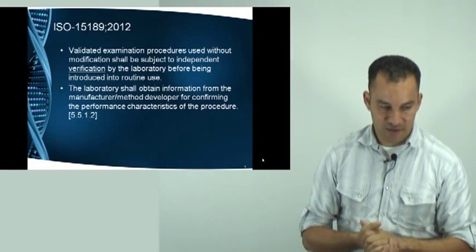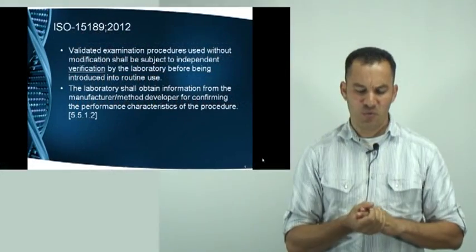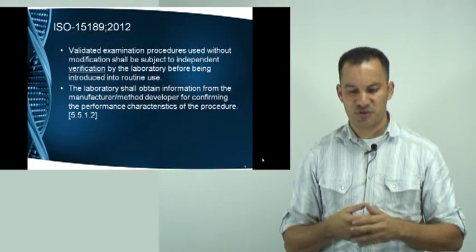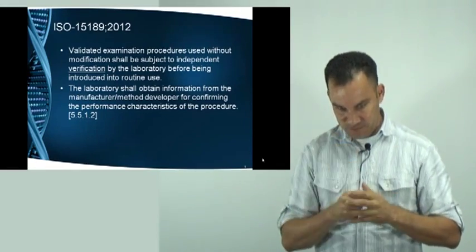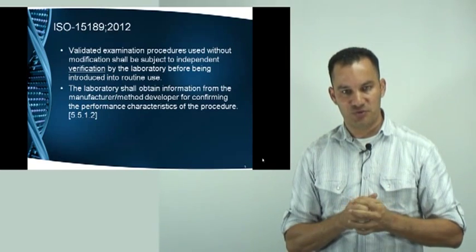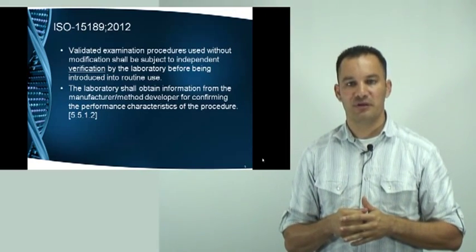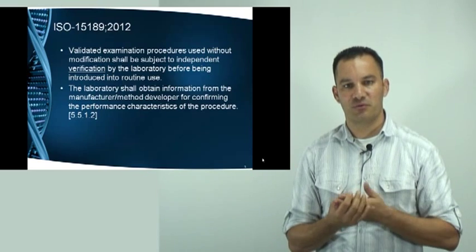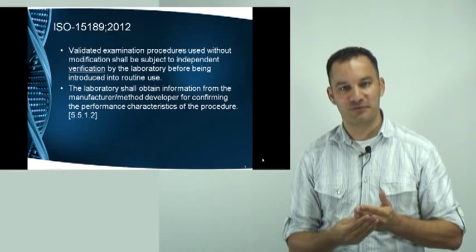It's also necessary to obtain information from the manufacturer or the method developer regarding performance characteristics: what is the precision, the between-run precision, the intermediate precision, the within-day precision, and the reference intervals. Any manufacturer nowadays should provide you with that information.